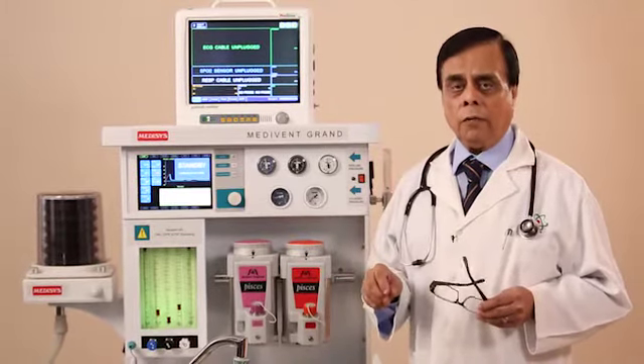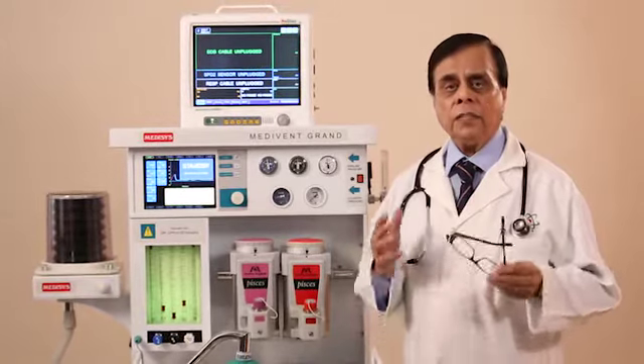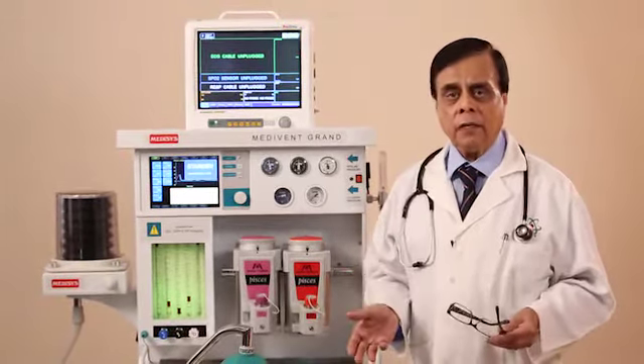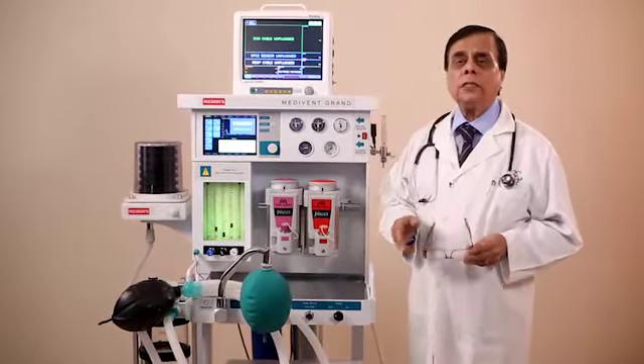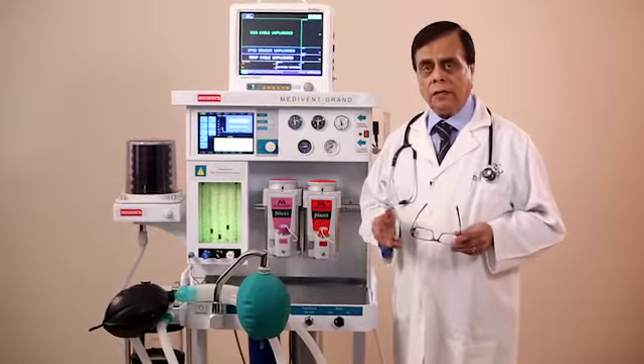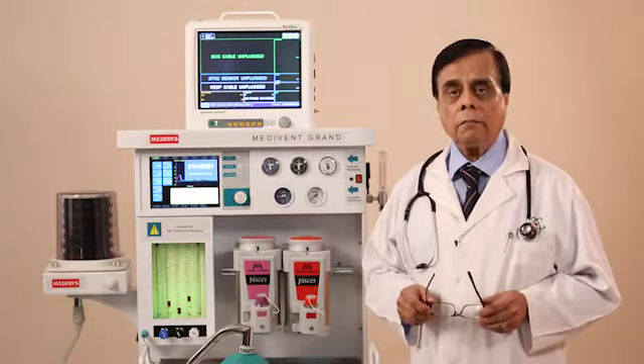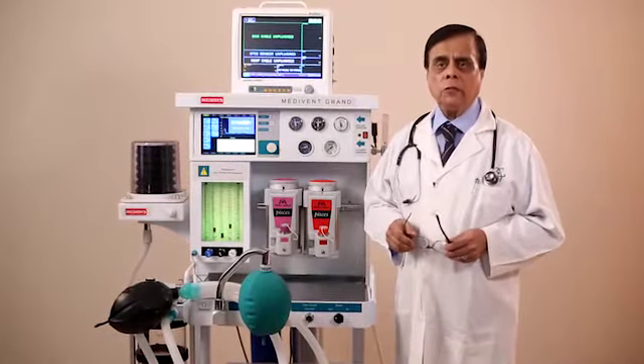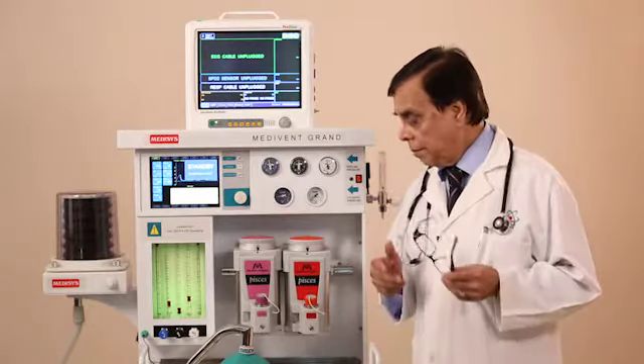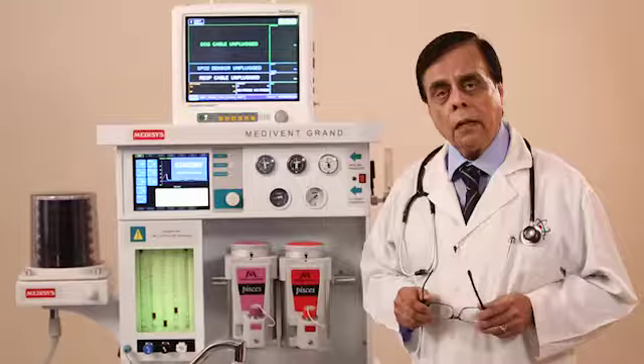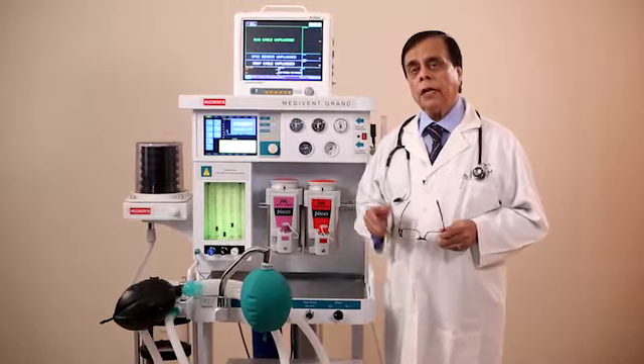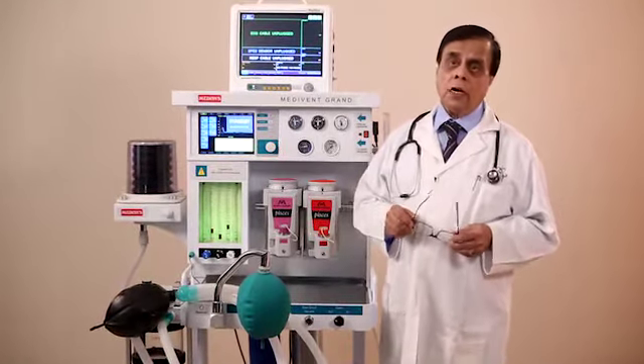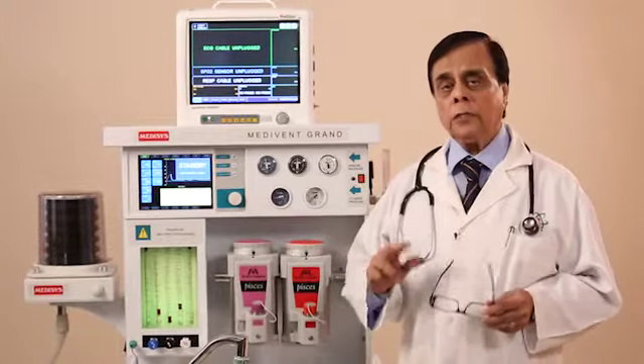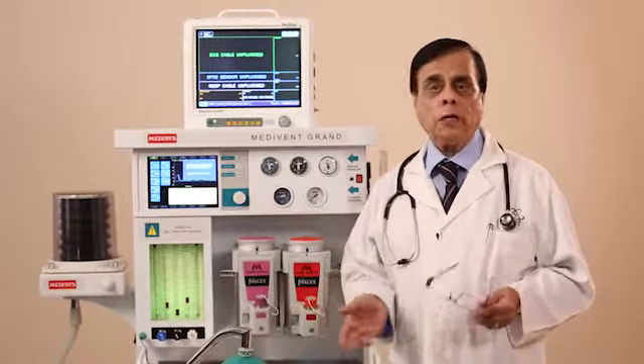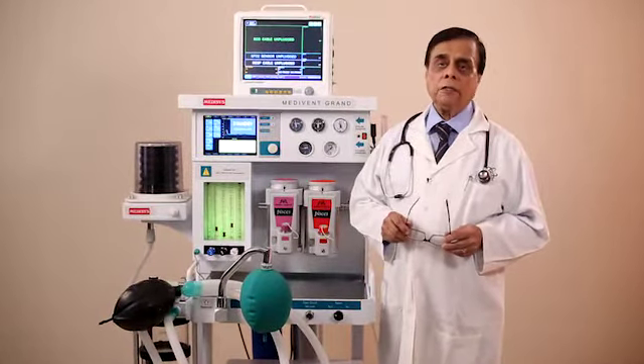And to do that, we have to have two devices. One is a safety device and second is the capability device. We talk about the safety device. The most dangerous thing which any anesthesiologist dreads is lack of oxygen delivery. To counteract that, we have several devices inbuilt into our machine. One of them is the oxygen ratio controller. Second is the oxygen failure protection device, and on top of that we have an inbuilt oxygen analyzer. This oxygen analyzer can also be interpolated between the inspiratory system and the expiratory system, so that you can know the expired oxygen concentration also.